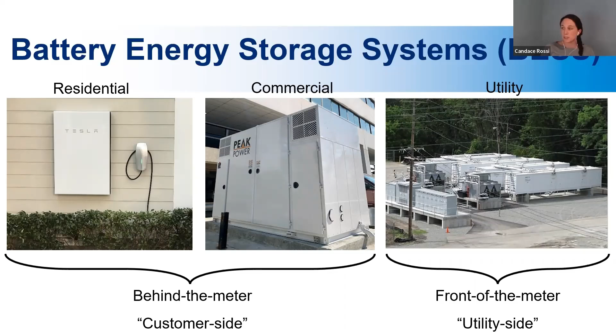To round out the impression of what these battery energy storage systems look like, there's the battery management system, probably the most important aspect of the entire system. This monitors each individual cell within the system, and will alarm if there are potential issues, such as temperature fluctuating inside the rack, and is able to isolate affected cells or modules from the total system. It's really the brains of the energy storage system, able to alarm on any abnormalities currently happening, which is extremely helpful and important.